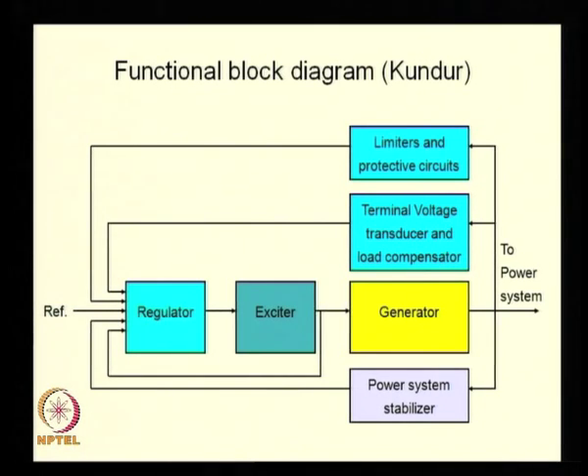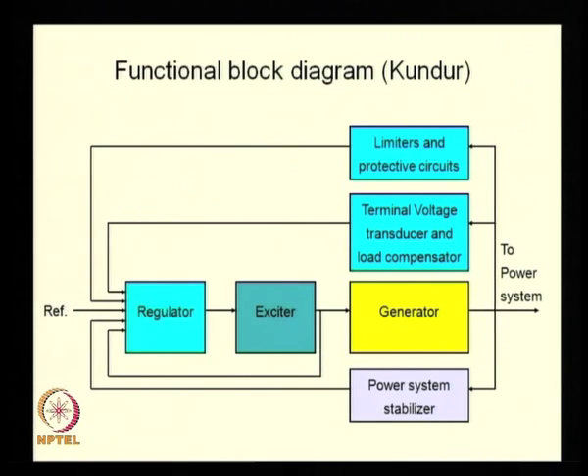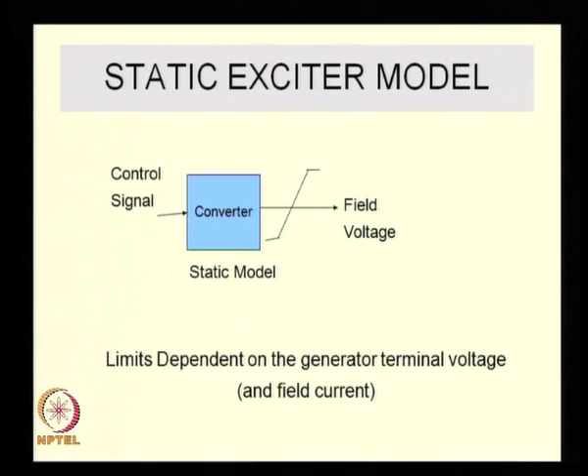We will use a simple model of an excitation system — a static exciter — and a generator connected to a power system. We will simply regulate the terminal voltage: the terminal voltage is measured and compared with the reference. We will not put any compensation for the load on the generator, so we will not have any component corresponding to the current output of the generator in the summing block. Simply, we will have V_ref minus V at the summing junction of the AVR. This is the model we will be using for the system.